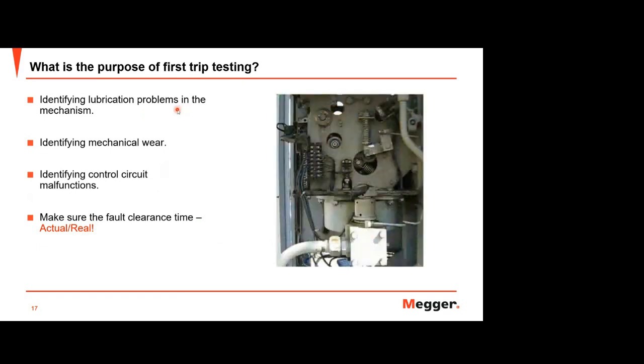And also identifying mechanical wear, as I mentioned, because all mechanical parts are metal and prone to corrosion, affected by environment conditions: temperature, humidity, and weather can affect the metal parts here. So if a breaker doesn't operate for a longer time, maybe 5 years, 10 years, it will of course affect the metal parts here. So as a first step we can verify whether all these conditions affected the mechanical parts or not.